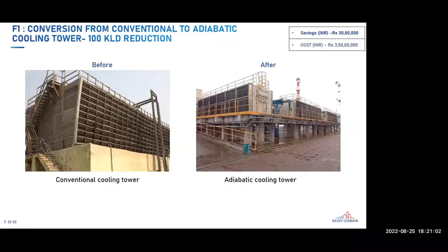When we did the cold repair in the years 2020 and 2021, we replaced this conventional cooling tower with an adiabatic cooling tower. In the adiabatic tower, the main difference is that the evaporation loss is completely zero. There is no evaporation loss. Only 30 to 40 KL of water is used for spraying, and that too can be recycled. The total investment of this project is 3.5 crores, and the savings is around 30 lakhs per annum.